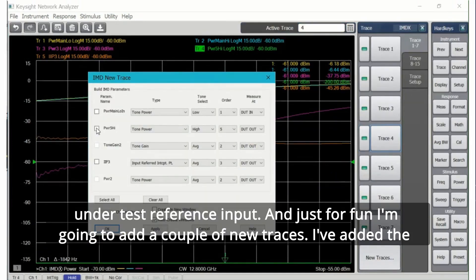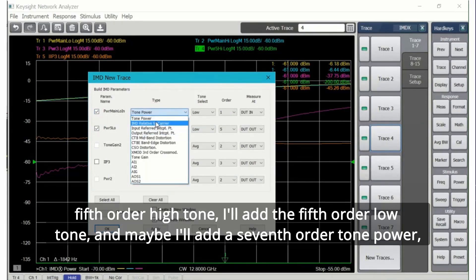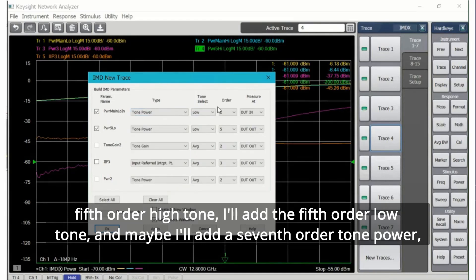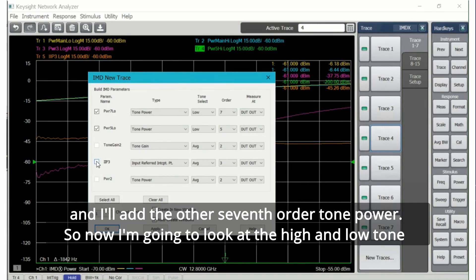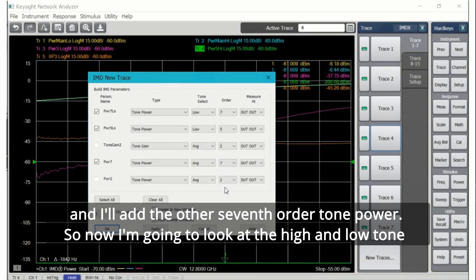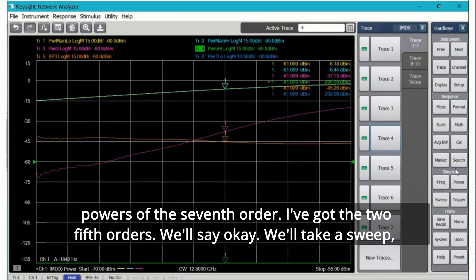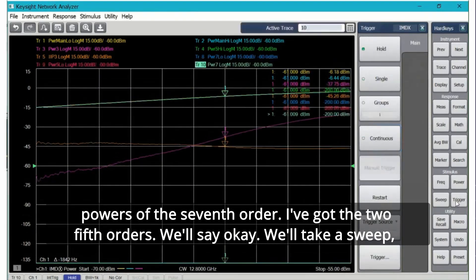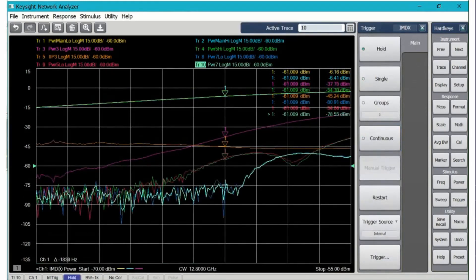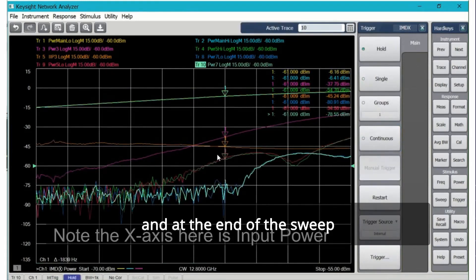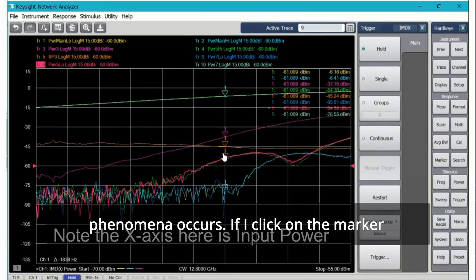Just for fun I'm going to add a couple of new traces. I've added the fifth order high tone, I'll add the fifth order low tone, and maybe I'll add a seventh order tone power. I'll add the other seventh order tone power so now I'm going to look at the high and low tone powers of the seventh order. I've got the two fifth orders. We'll say okay, we'll take a sweep. At the end of the sweep we can see that an interesting phenomena occurs. If I click on the marker and move the marker across the trace, I can see that in this region the fifth order power has a minimum.